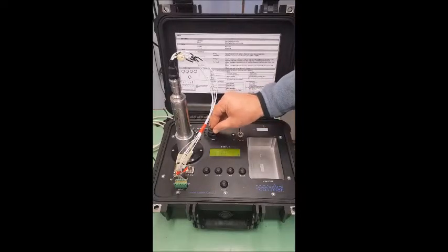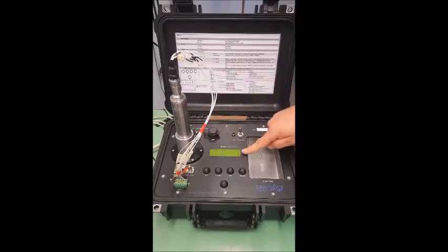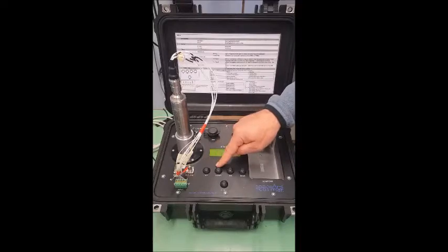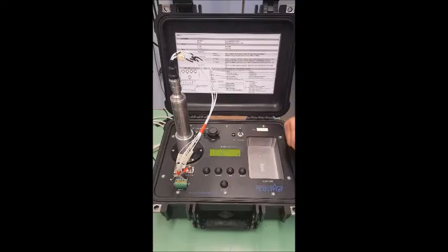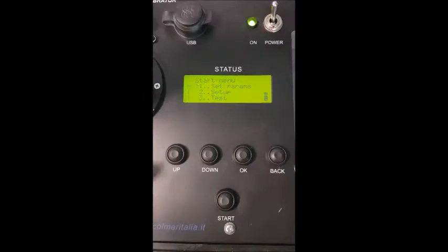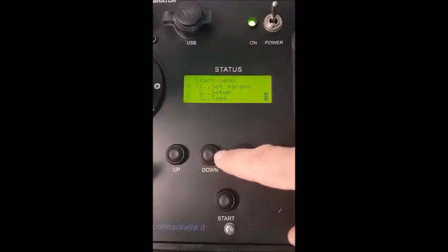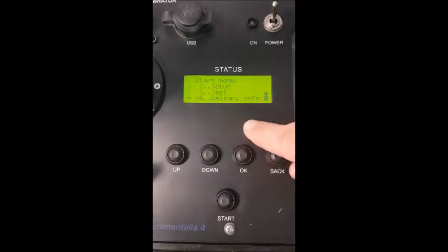Also, we have the display of the device. Via this display and the user buttons, we can navigate a user interface and set up and start a calibration. The buttons are up, down, OK, back. This enables the user to navigate the interface, and the start button is used to start an actual calibration. This you see here is the main menu of the user interface of the calibrator. The main menu has 4 sub-menus: set parameters, setup, test, and calibrator info.